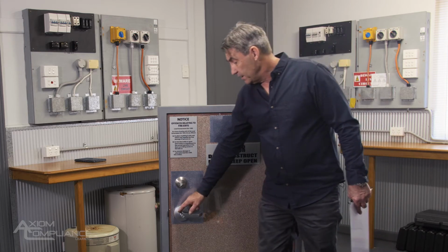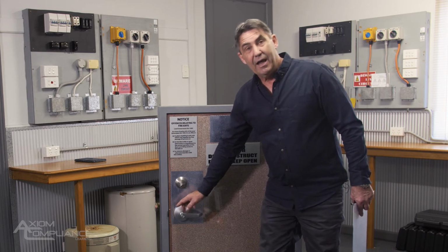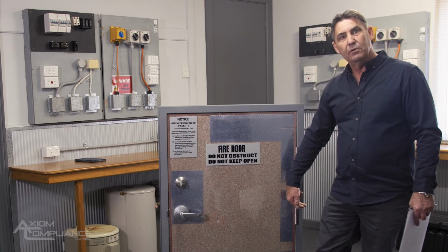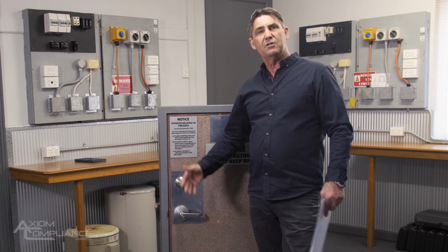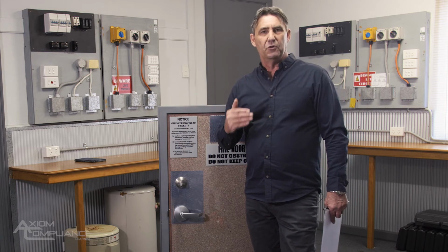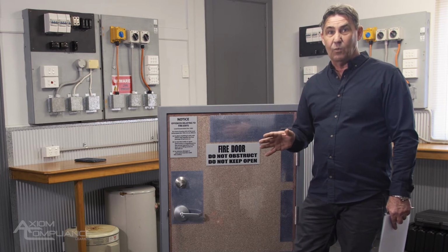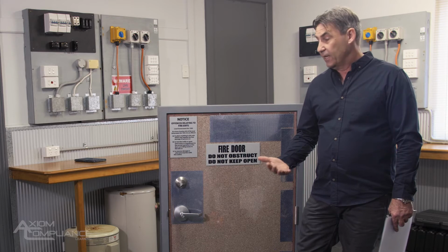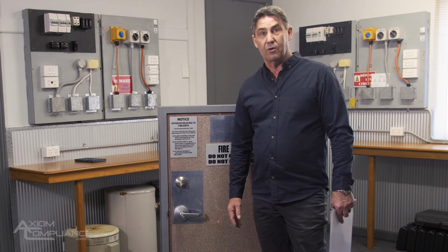I've got to look at the serial numbers of the hardware and check with the manufacturer of the door set, which is named on the label, whether that hardware is suitable for this door. And once I've established that, I can start a register of doors and I can create my baseline data. This has only got to be done once, and it's worth doing. You cannot inspect the door correctly unless you've checked that the hardware is the right type.